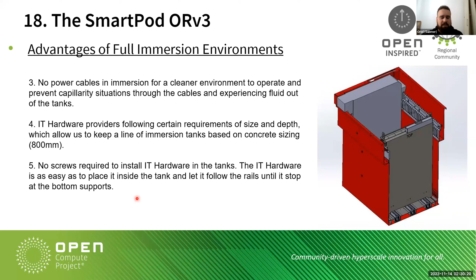We have the same tank design for everything because the OCP standard respects 800 millimeters, so we don't need to adapt the tanks as the IT hardware industry changes over time. Also, no screws are required to install or remove IT hardware inside the tanks; components just follow the rails and stop at the bottom of the tank. This avoids screws falling to the bottom of an immersion tank, which can create a risk, as we'll discuss with the 19-inch EIA brackets.